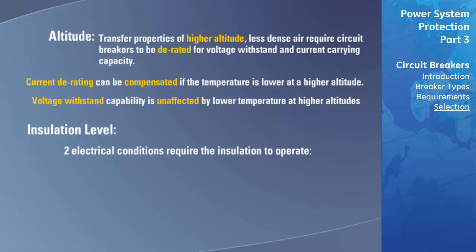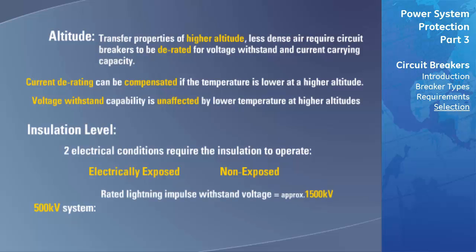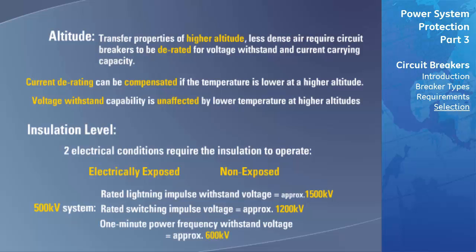There are two separate electrical conditions under which insulation may be required to operate: electrically exposed and non-exposed — essentially whether the insulation is mounted indoors or outdoors. Outdoor switchgear is exposed to atmospheric conditions such as lightning, which can cause overvoltages. For a 500 kilovolt system, the rated lightning impulse withstand voltage is approximately 1500 kilovolts, the rated switching impulse voltage is approximately 1200 kilovolts, and the one-minute power frequency withstand voltage is approximately 600 kilovolts.